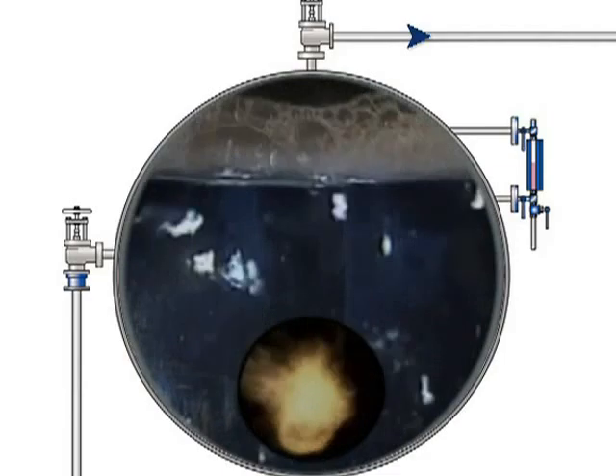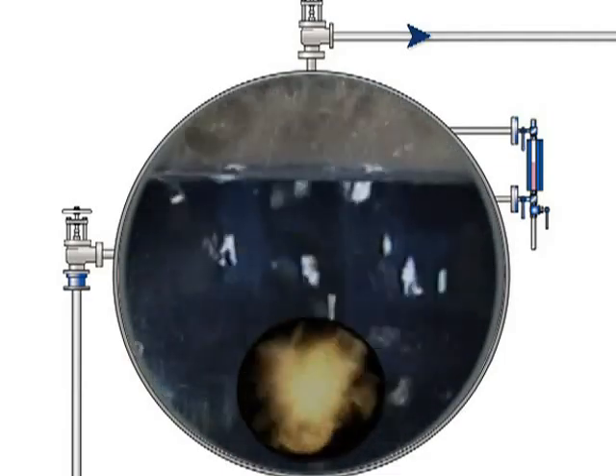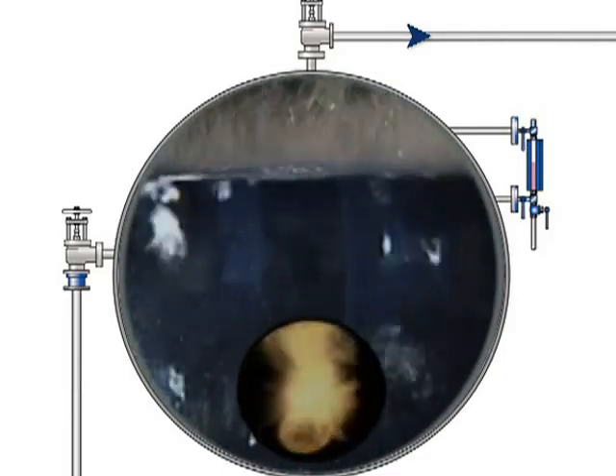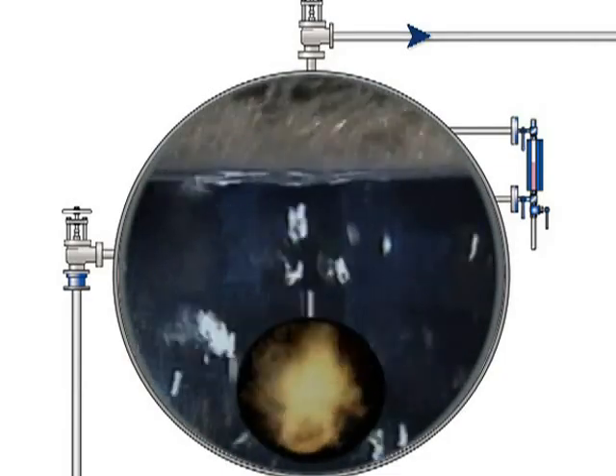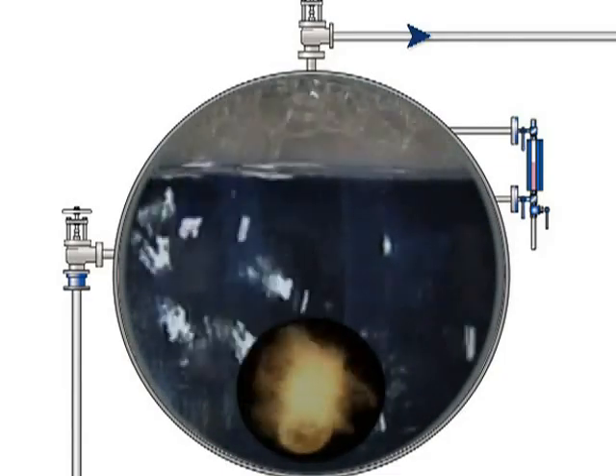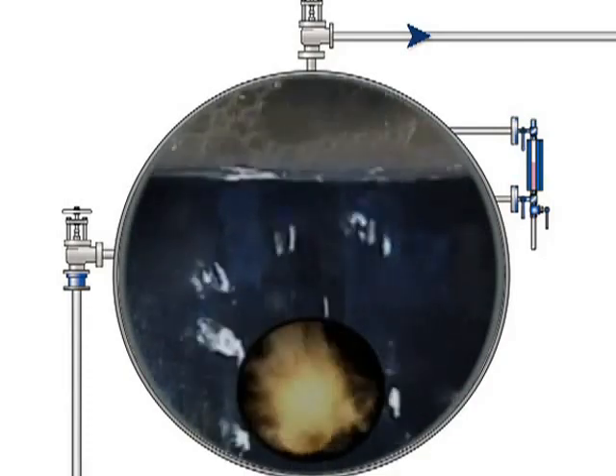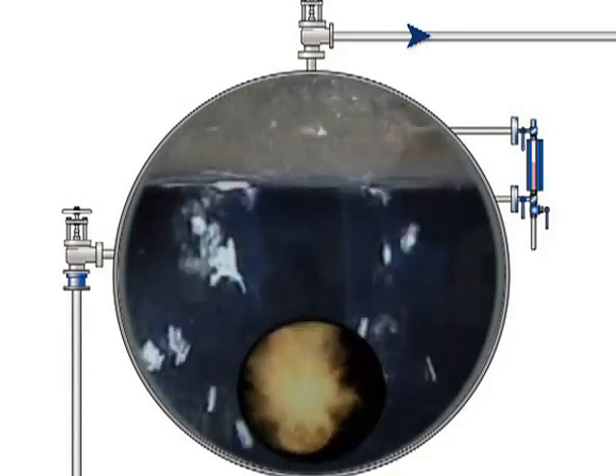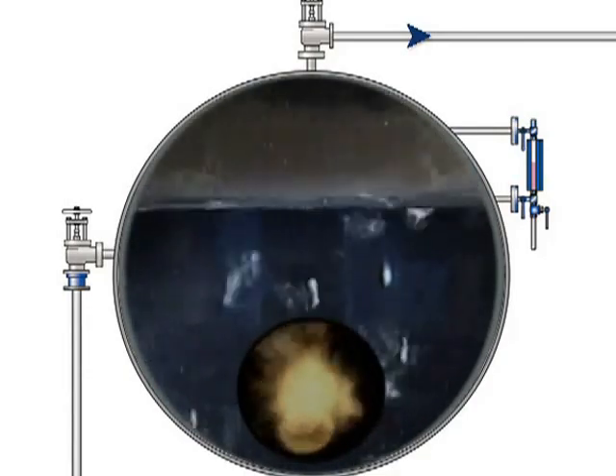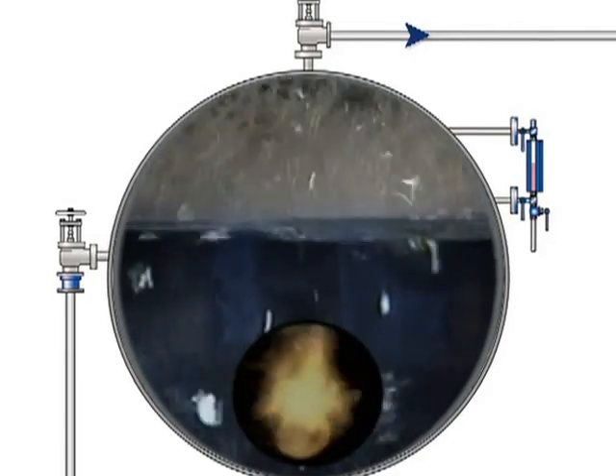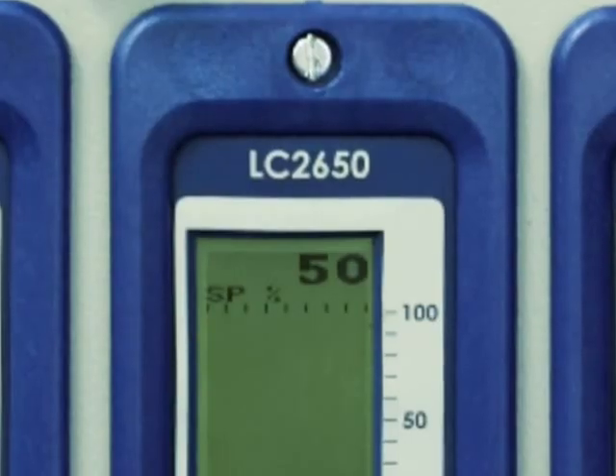None of this is apparent in the gauge glass or the protection tube because they are measuring virtually bubble-free water, and the water at the top of the boiler consists mainly of steam bubbles. The measured levels begin to fall as water continuously flashes into steam in the boiler's attempt to satisfy the excessive demand.